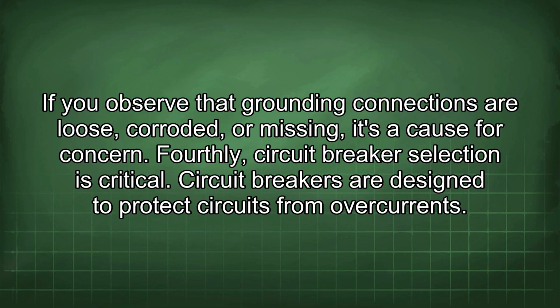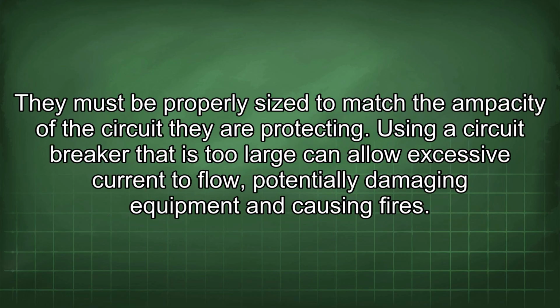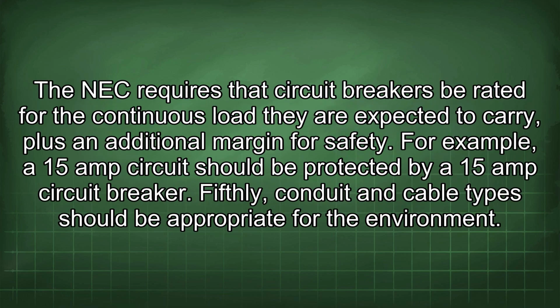Fourthly, circuit breaker selection is critical. Circuit breakers are designed to protect circuits from overcurrents. They must be properly sized to match the ampacity of the circuit they are protecting. Using a circuit breaker that is too large can allow excessive current to flow, potentially damaging equipment and causing fires. The NEC requires that circuit breakers be rated for the continuous load they are expected to carry, plus an additional margin for safety. For example, a 15-amp circuit should be protected by a 15-amp circuit breaker.